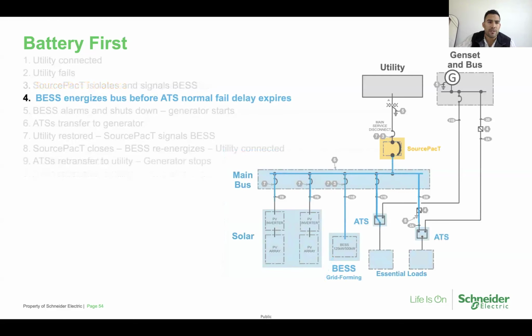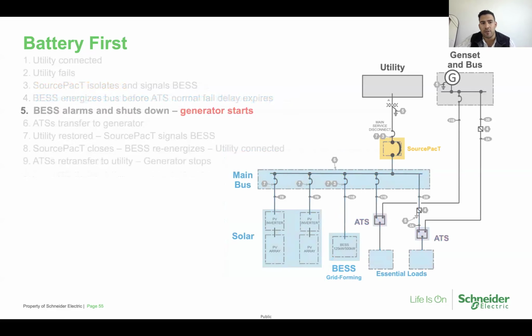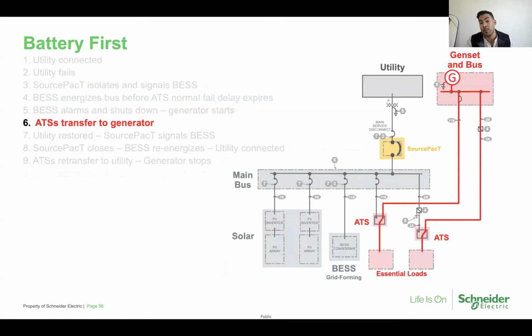So let's just say we go through this animation, your backup power through the energy storage system, your loads and ATS are still connected to source one. In the event that your battery energy storage system hits the low reserve, or it's coming close to the 10-20% of its state of charge, at that point, the energy storage system will shut down. And that's where your ATSs come in. And now your ATSs will transfer from source one, where that energy storage system was providing power, now to the generator, where it called on the generator.